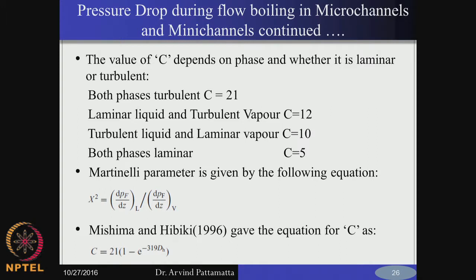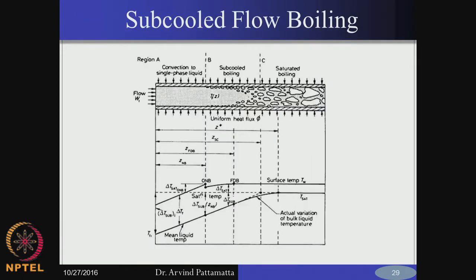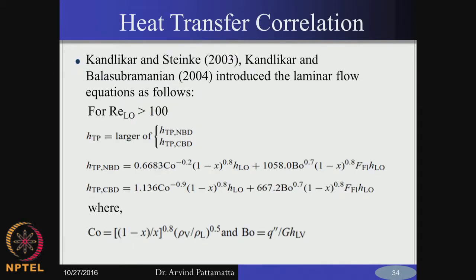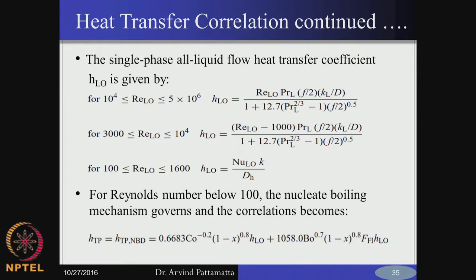You estimate the Chisholm parameter C depending on whether the flow is turbulent or laminar — you have to check for either phase. The vapour could be turbulent while the liquid is laminar, which is more often the case since vapour velocity is higher than liquid. Now going into heat transfer — there are no analytical methods to calculate the heat transfer coefficient H for two-phase flows the way we have for single phase. We generally have two regimes: one for laminar flow and one for turbulent flow.